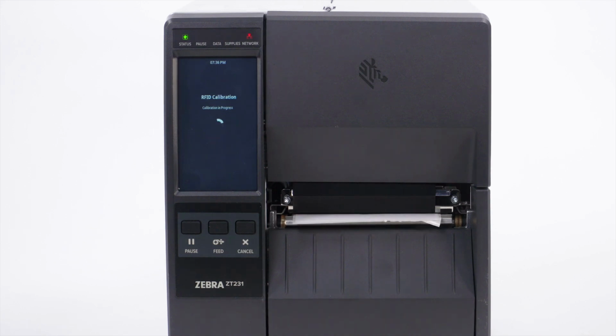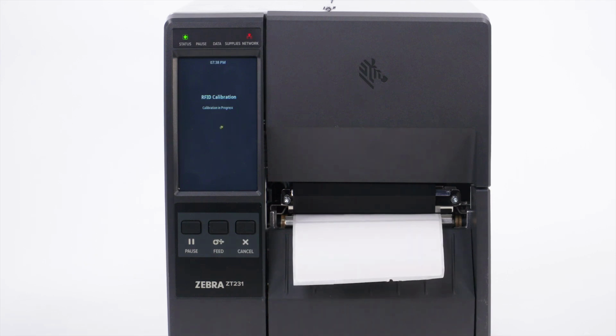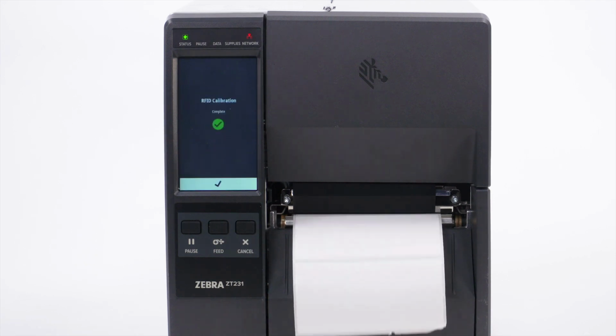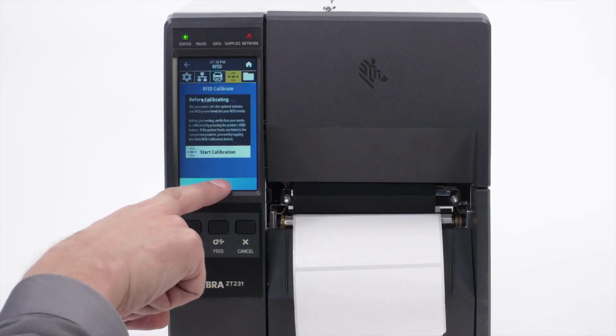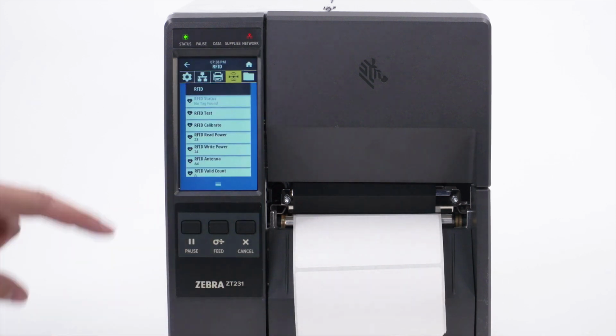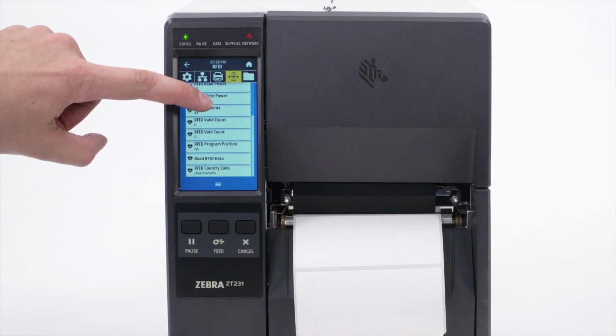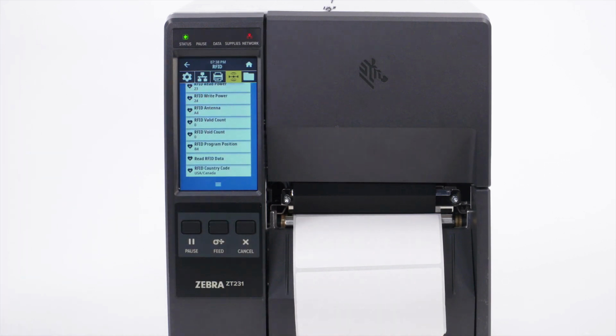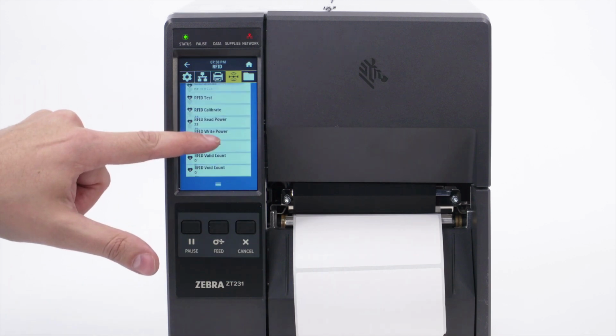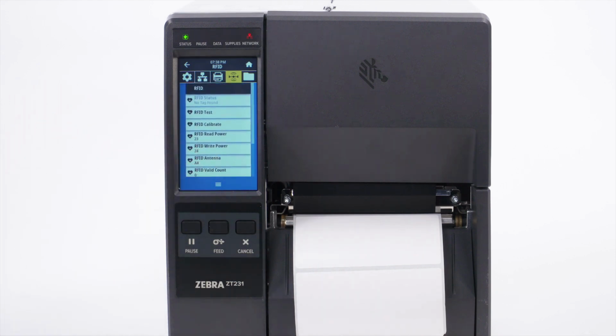The printer will move the label incrementally during the calibration while testing the RFID inlay to determine the optimal RFID settings. A successful RFID calibration will display RFID calibration complete. Touch the check. You can view the new RFID settings in the RFID menu. Scroll to review the RFID settings. Any labels used in the RFID calibration can be wound back onto the media roll.